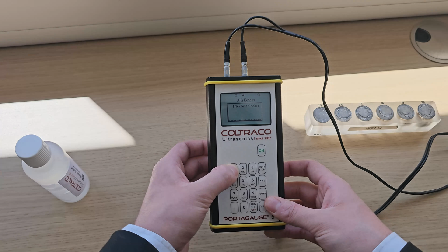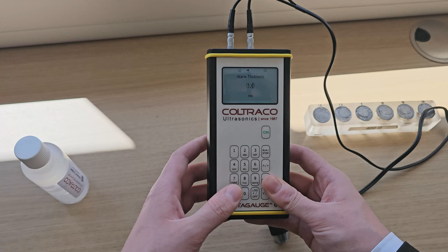First of all, I'd like to show you the minimum thickness alarm. So I'll press 1 to bring me back to the main menu. I'll go into System. I'll go all the way down to Calibration. And in calibration, I can come down to alarm thickness here. You see at the moment this is set to 0mm, which means that the alarm is off. But let's say I'm testing something and I need the thickness to be no less than 5mm thick.